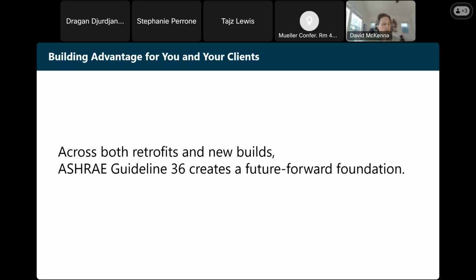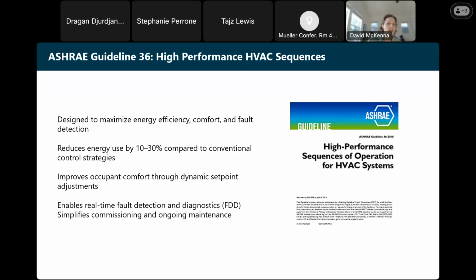One of the main topics I'm going to be talking about is ASHRAE Guideline 36. This affects both types of buildings that we just talked about. There is ASHRAE 90.1, which is the design minimum standard, which we design to as engineers and architects. But ASHRAE Guideline 36 goes above and beyond. Every year we're seeing the energy code push us in that direction year after year. So as design engineers, this is becoming the new standard to which a lot of engineers and firms are designing to. And we'll see why in these next couple slides.